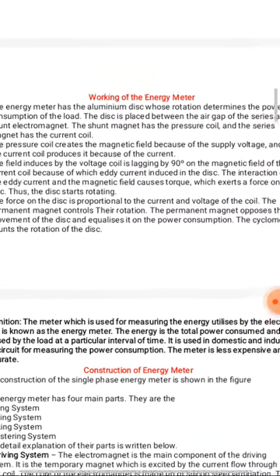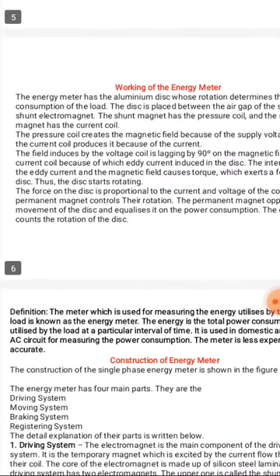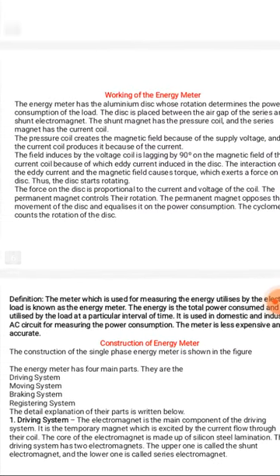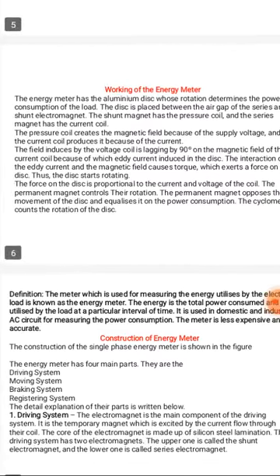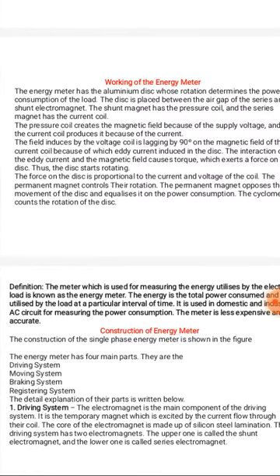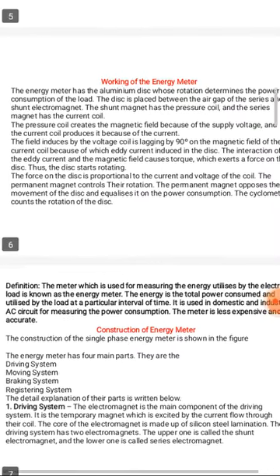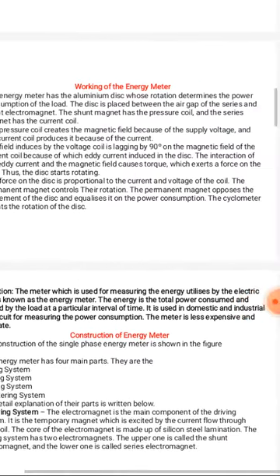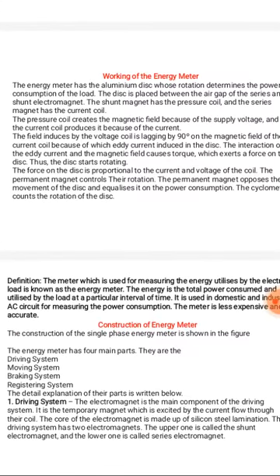The disc is placed between the air gap of the series and shunt electromagnet. The shunt magnet has the pressure coil and the series magnet has the current coil. The pressure coil creates the magnetic field because of the supply voltage and the current coil produces it because of the current. The field induced by the voltage coil is lagging by 90 degrees on the magnetic field of the current coil, because of which eddy current is induced in the disc. The interaction of the eddy current and the magnetic field causes torque which exerts a force on the disc. The disc starts rotating.